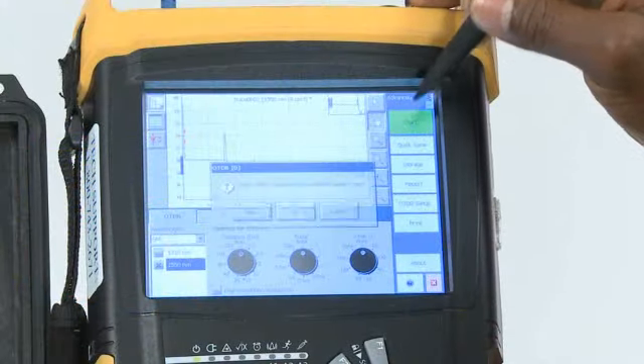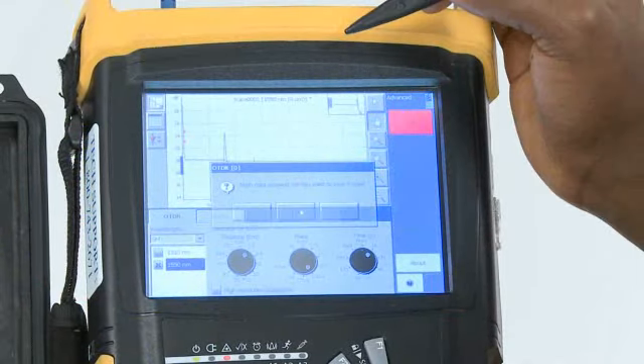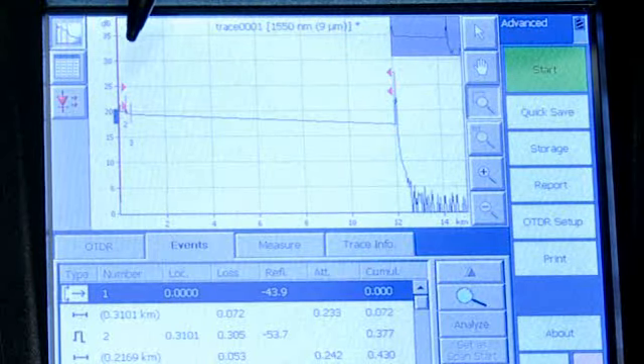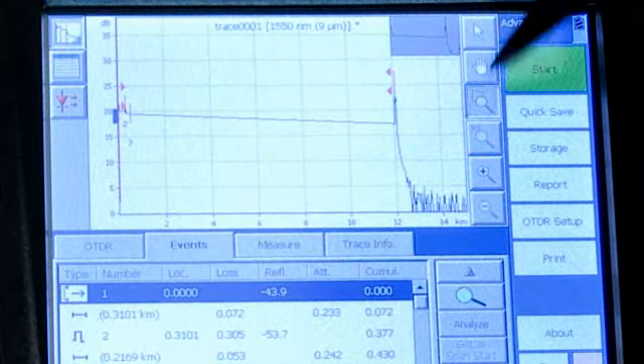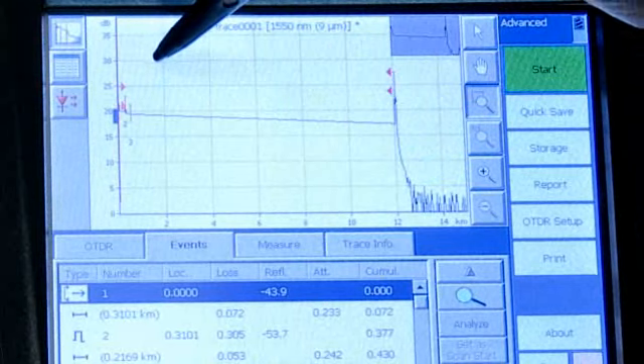We can now shoot a trace across the whole system. After the preset acquisition time has expired, I can see that my trace is about 13 kilometers long, and most of the events are concentrated around the beginning.